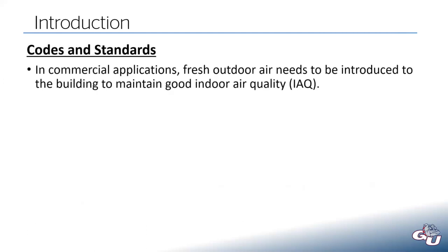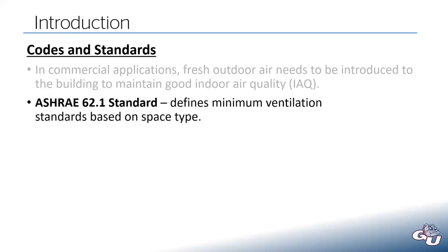Another standard worth talking about in commercial applications. I mentioned earlier that fresh outdoor air needs to be introduced to the building to maintain a certain level of indoor air quality, which we normally don't see in residential applications, but in commercial buildings, it's a big deal. We need to bring in that fresh air to keep the occupants nice and healthy. The standard is called ASHRAE 62.1, which defines the minimum ventilation requirements based on the space type.